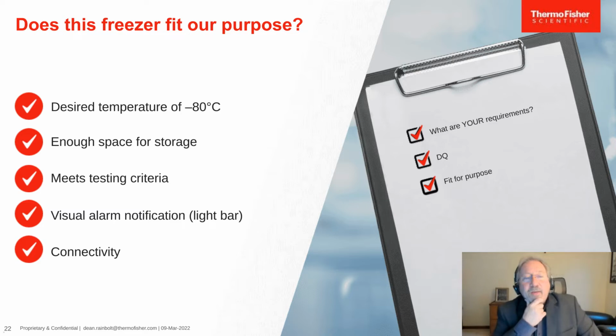Now, everything that we looked at with that TDS and all the information per the regulations, we need to double check and make sure that this freezer fits our purpose. So, desired temp of minus 80. Yep, that fits. Do we have enough space for storage? Well, I didn't focus on it on the TDS, but this particular freezer has about 28 and some change cubic feet of storage space. So that's close enough for the 30 that I was looking for.